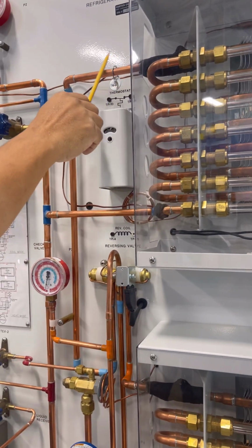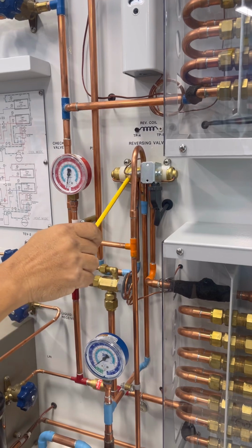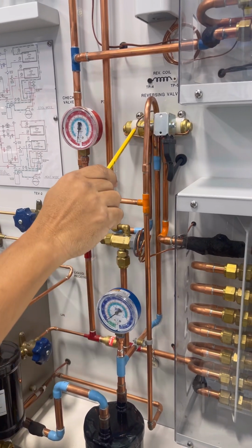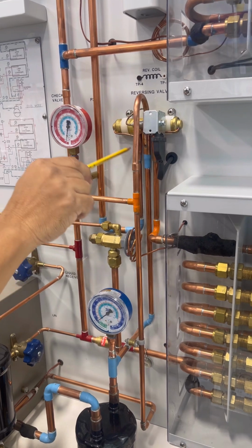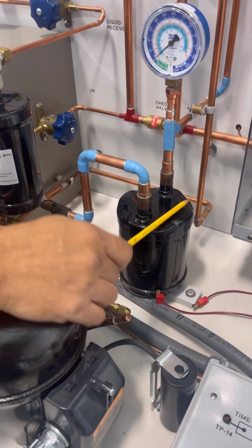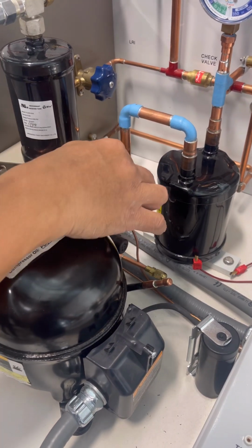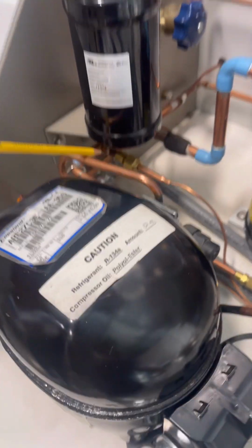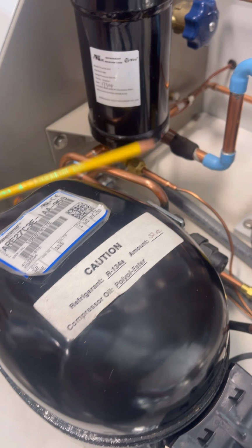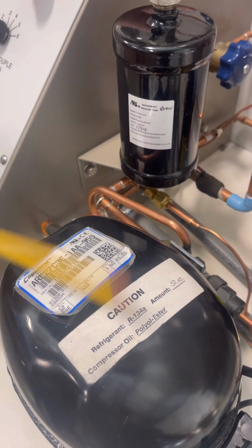Now it comes out vapor, and it goes back to what we call the reversing valve, and it goes to the middle. So right here, before the freon goes in here, the valve goes to the right, and that gives the freon access from this side over here, goes to the middle, and goes straight back to the accumulator. The accumulator is the one that separates the moisture and the oil from the freon. And then this goes back all the way to the big line, which is what we call the suction line. And the pressure is changing here. The pressure is 118, and the temperature is 55 degrees Fahrenheit. And it goes inside.